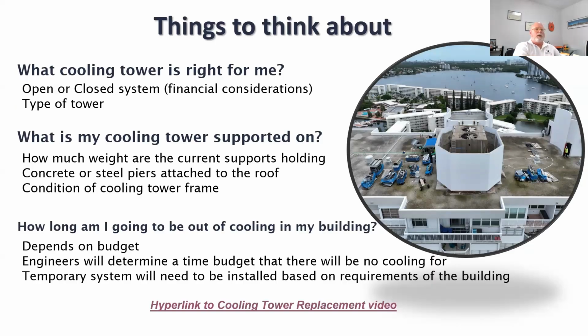As I've talked about multiple times, cooling towers frequently require changes and modifications to the structures holding them. As codes have increased, wind loading has increased, which has increased the loads required on the supports. So while it may have been fine 30 or even 20 years ago, it's not today, because wind load speeds have increased under current code. That's something that really needs to be looked at — it could be the big issue, and it's flushed out a lot during the design process.